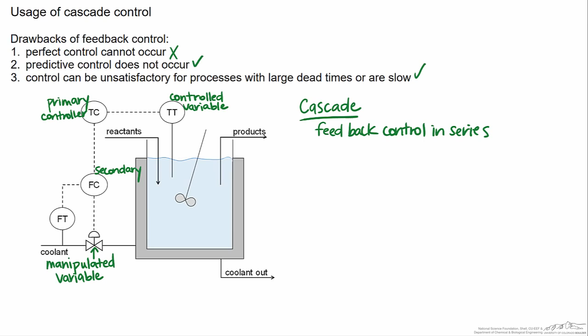So the temperature controller is represented as the primary controller. The primary controller in a cascade control scheme will always be the controller that corresponds to the controlled variable, in this case the reactor temperature. And the flow controller is the secondary controller: primary, secondary. There can be more than 2 layers of cascade control, so it can be ternary, quaternary, etc. Whatever is lowest in the hierarchy is the one that will directly control the valve.